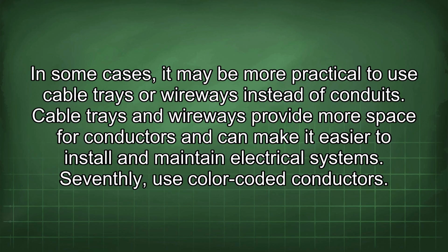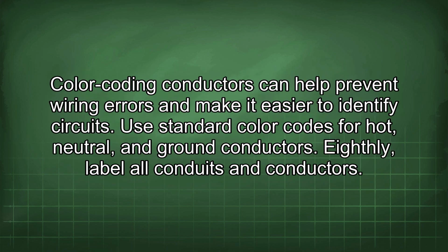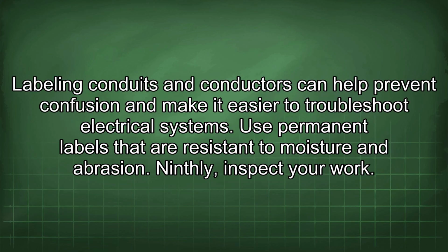Seventhly, use color-coded conductors. Color-coding conductors can help prevent wiring errors and make it easier to identify circuits. Use standard color codes for hot, neutral, and ground conductors. Eighthly, label all conduits and conductors. Labeling conduits and conductors can help prevent confusion and make it easier to troubleshoot electrical systems. Use permanent labels that are resistant to moisture and abrasion.